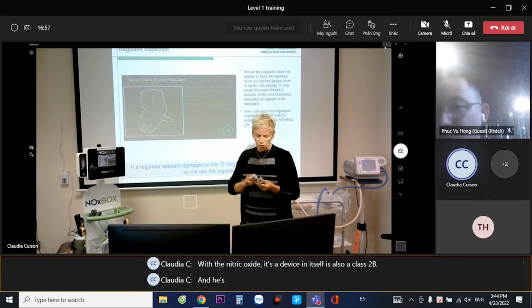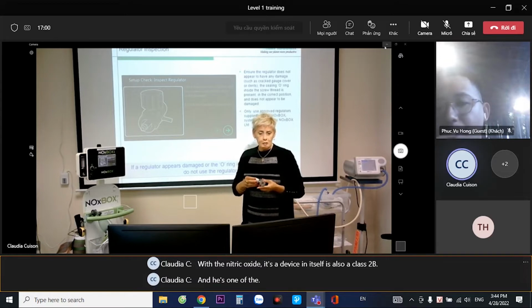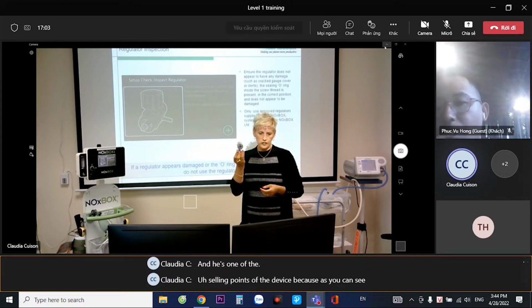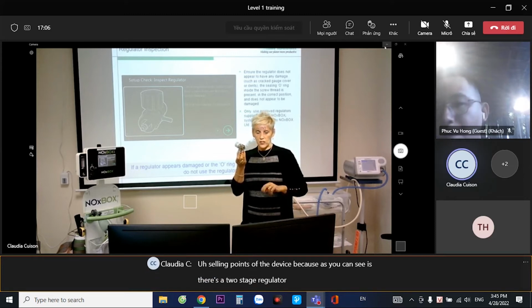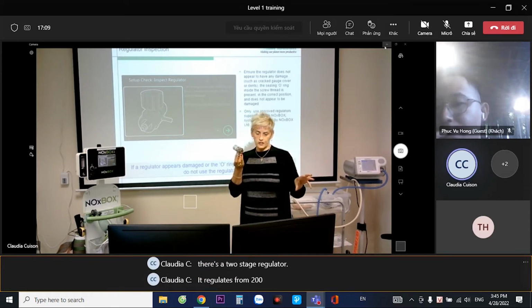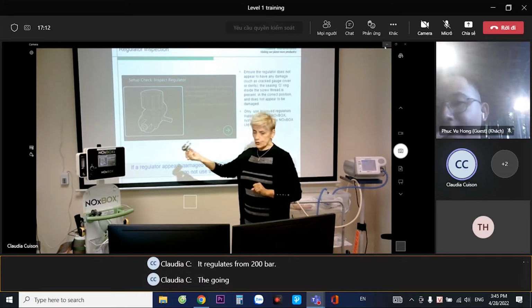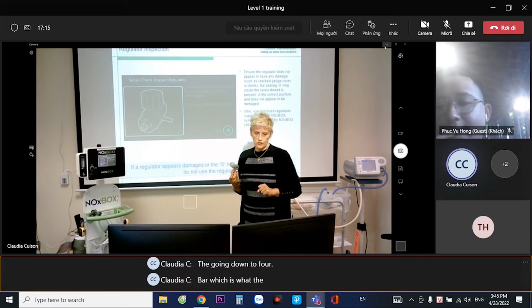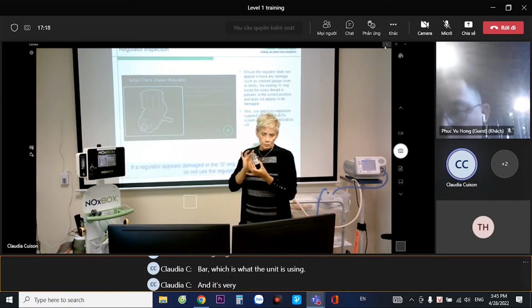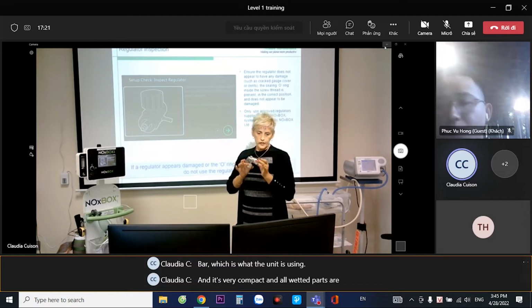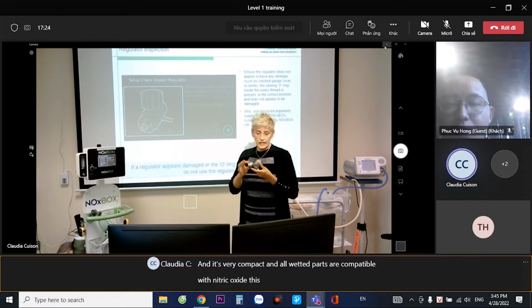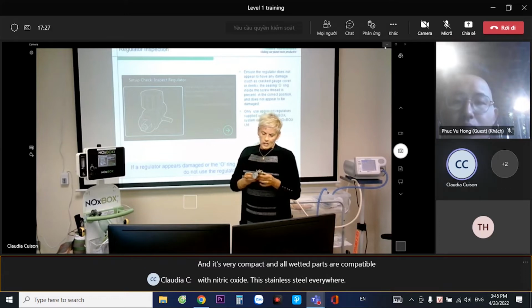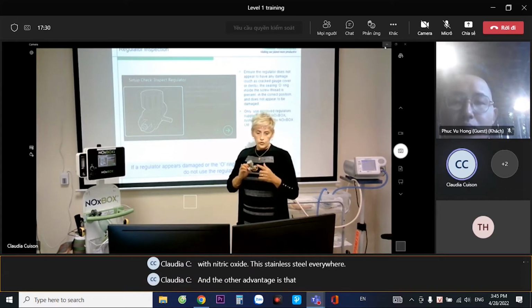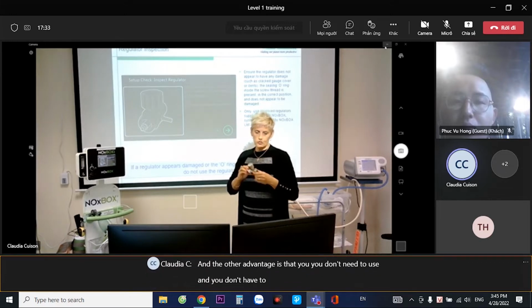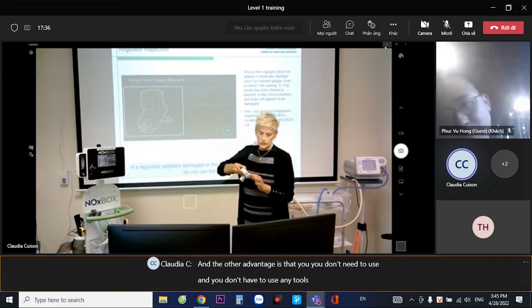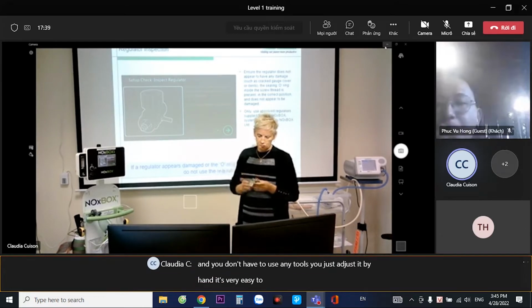It is one of the selling points of the device, because as you can see, it is a two-stage regulator. It regulates from 200 bar going down to 4 bar, which is what the unit is using. It's very compact, and all wetted parts are compatible with nitric oxide. It's stainless steel everywhere. The other advantage is that you don't have to use any tools. You just adjust it by hand. It's very easy to adjust.